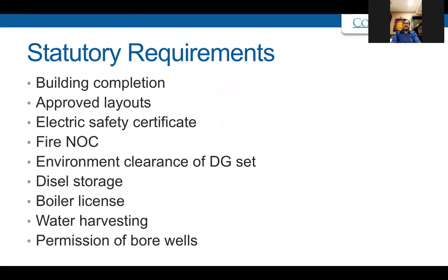Boilers: most of the hospitals have actually abandoned boilers because there is no need of them. Earlier a boiler was required due to the requirement of laundry in the hospital. But nowadays everybody has outsourced laundry, so most hospitals have only water calorifiers and not boilers. And even government permits the use of small boilers in the CSSD for your sterilization equipment. So boiler license is not that much of a problem, but if a boiler is there on site, then the boiler license has to be obtained from the explosive authority.